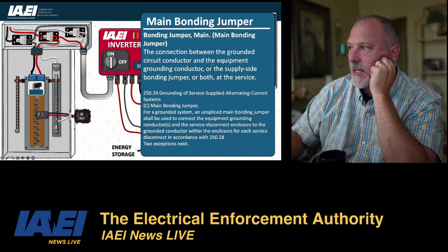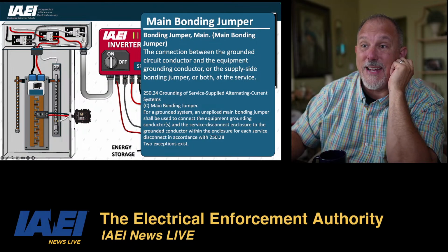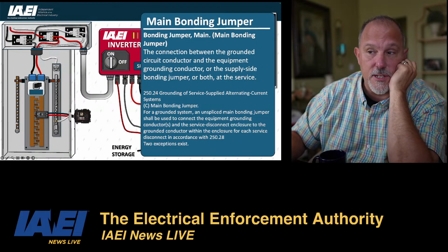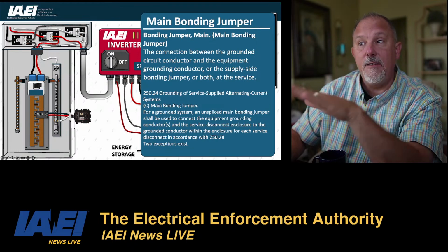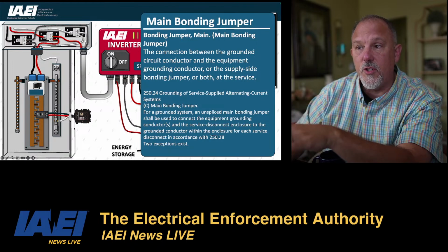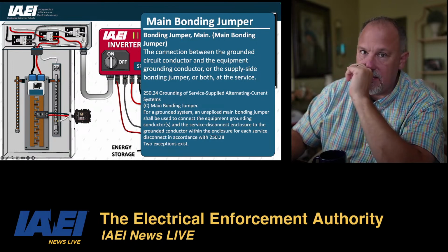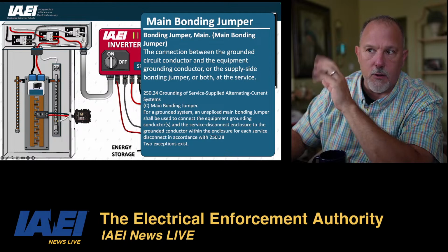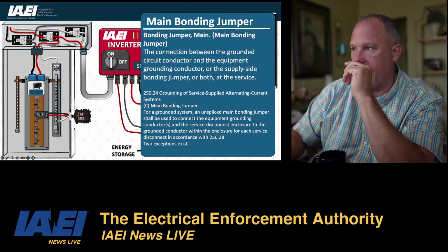The grounded circuit conductor and the equipment grounding conductor. So that's this. The equipment grounding conductor is this bar over here. And in many service entrance panel boards, we will have that. And we talked about this in one of the first sessions of Article 230. Those two will be bonded.